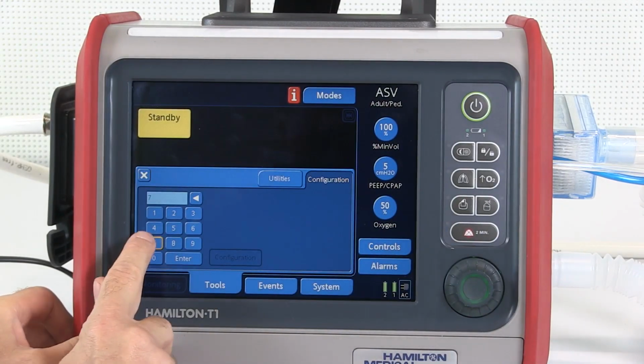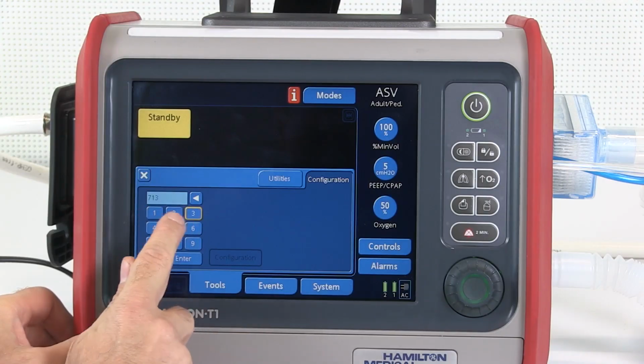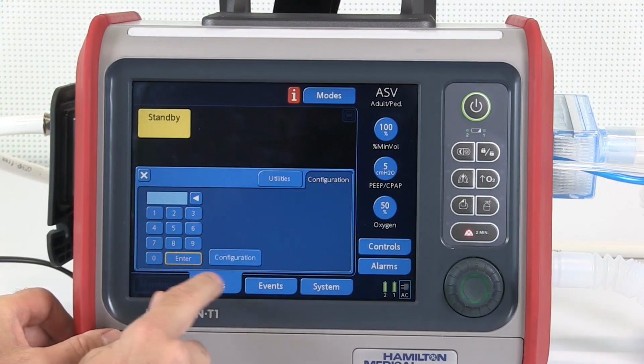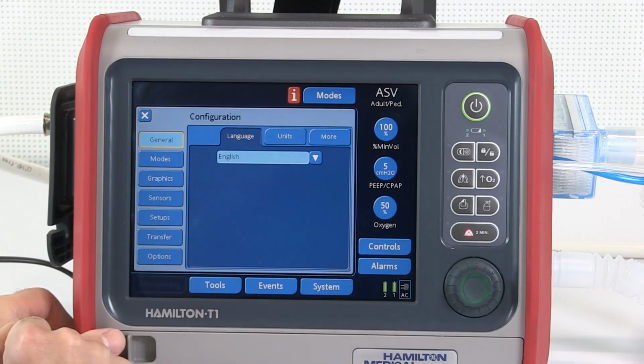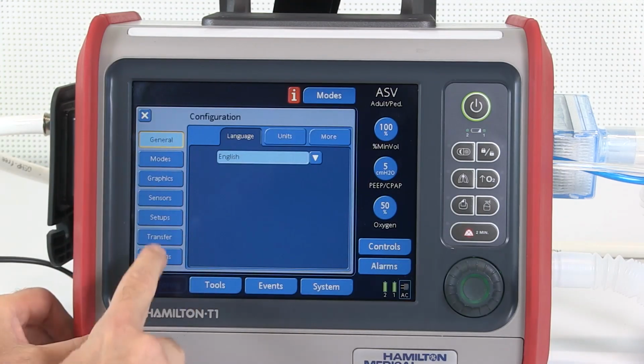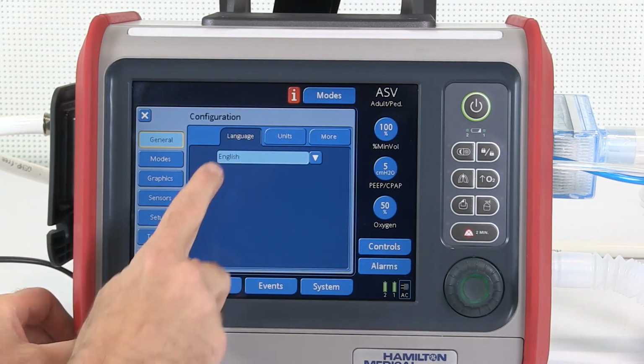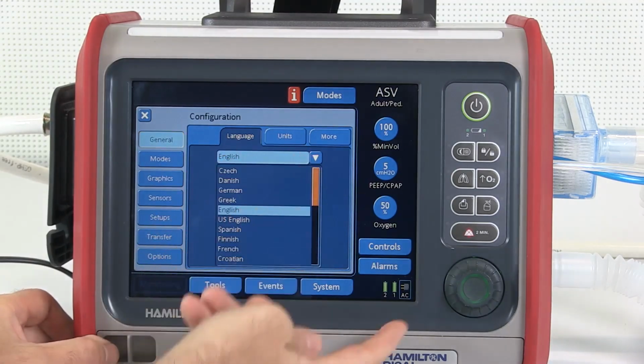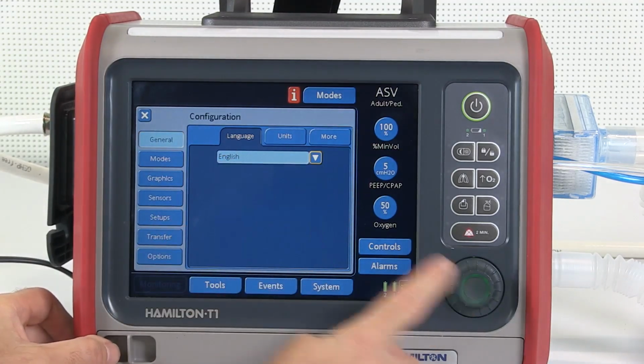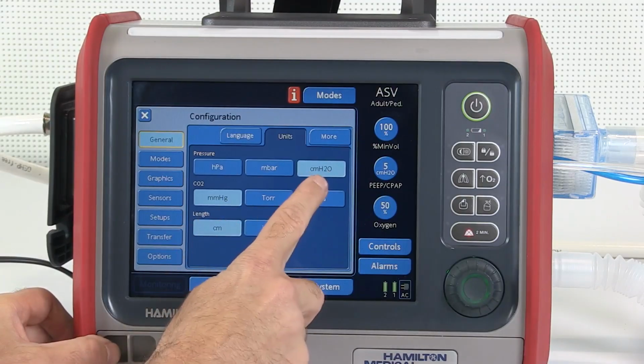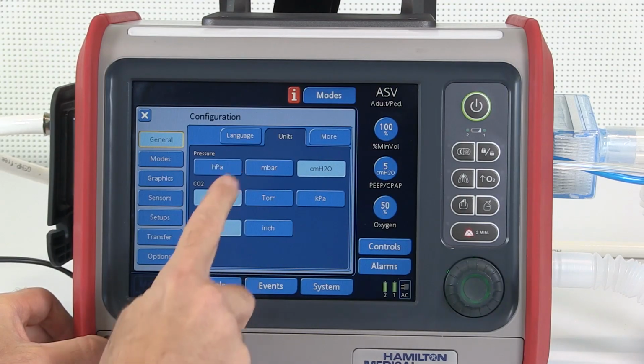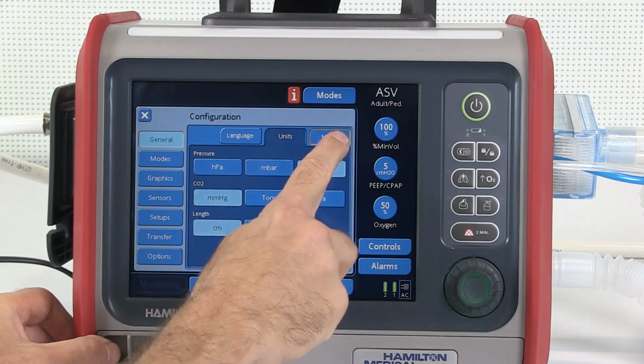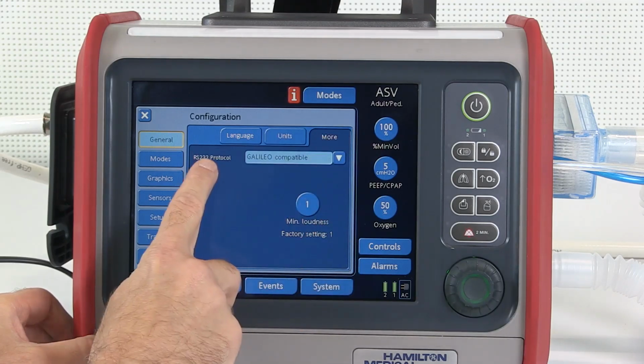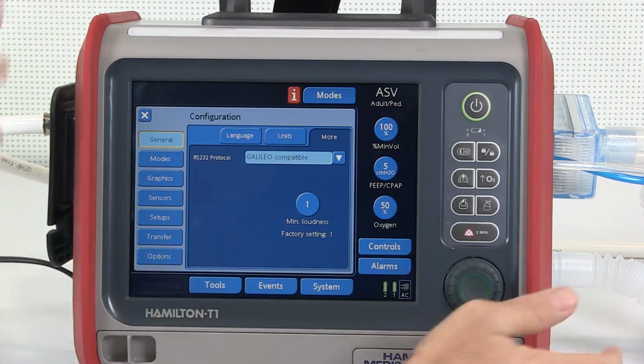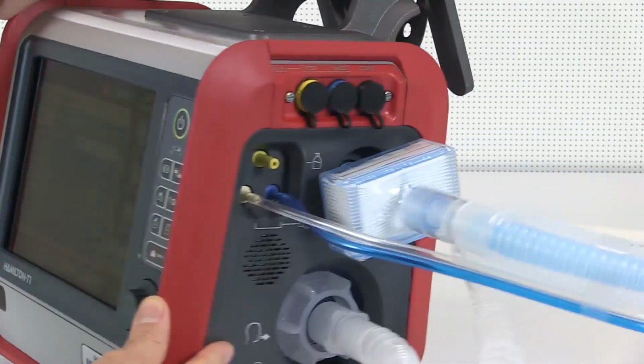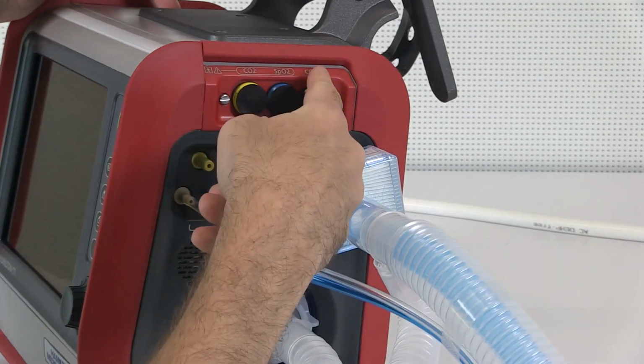Enter the configuration code 7132, followed by Enter and Configuration. On the left, you can select the available configuration settings. Select the desired language for this ventilator unit. Touch Unit to select the appropriate unit of measurements for pressure, CO2 and length. Touch More to set the desired RS-232 protocol to communicate over the COM1 port if installed as an option.